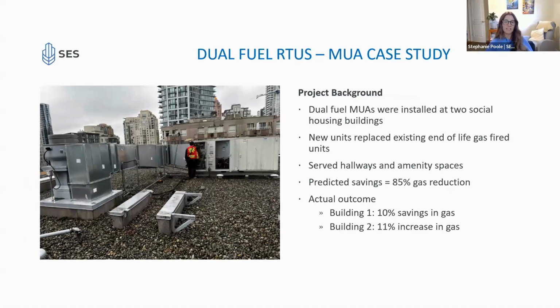Okay, wonderful. Thanks. So as I said, the reason that we're focusing on these dual fuel rooftop units is because they have a lot of potential. You can see up to 30 to 90% savings of your gas, depending on how well it's performing. But what we're seeing is that they're not performing.